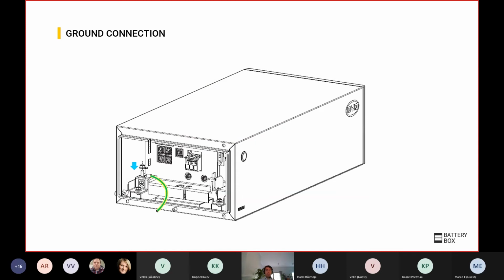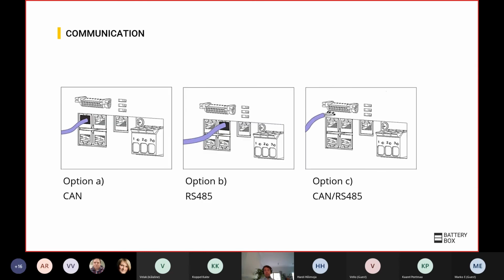So always start with the ground connection, because this one is not only from a safety point of view, but it can also affect the communication with the inverter, so the quality of the signal with the inverter. So make sure that it's always properly grounded to the grounding of the house. The second step will be the communication connections. First one is the one to the inverter.